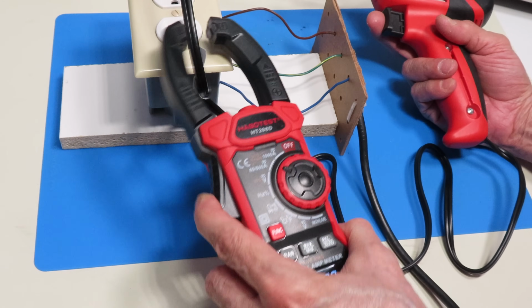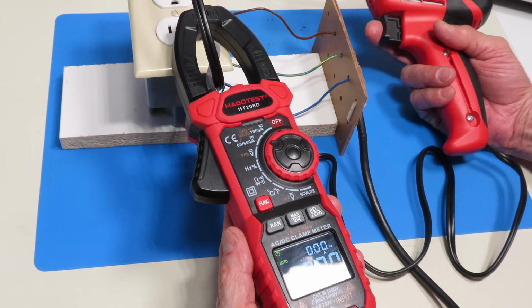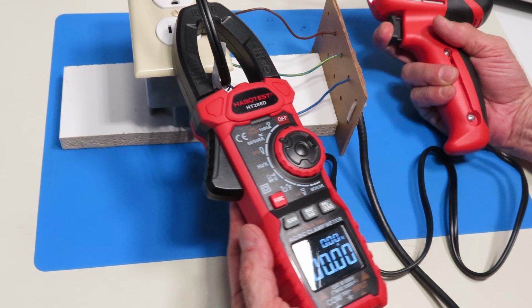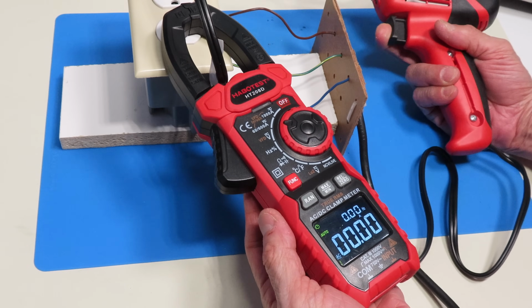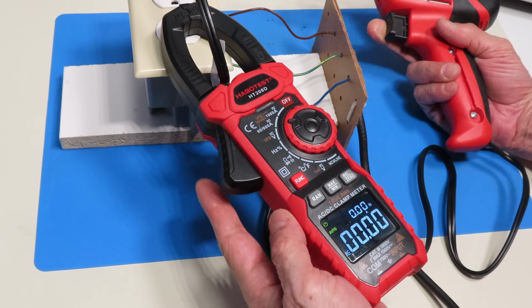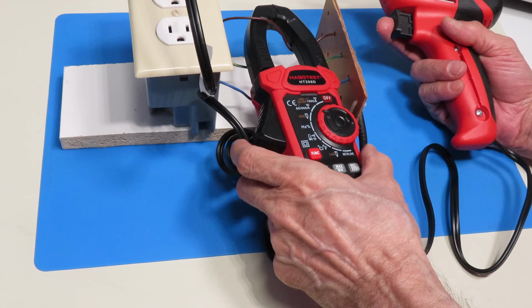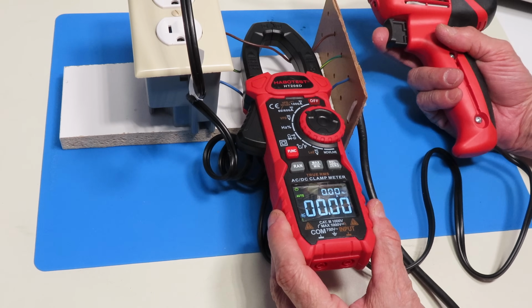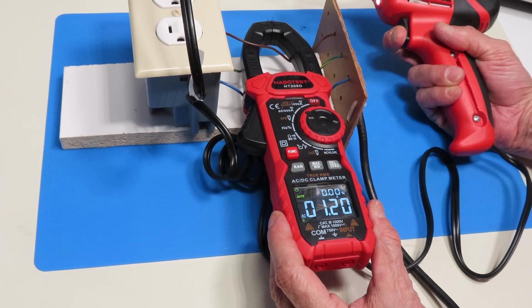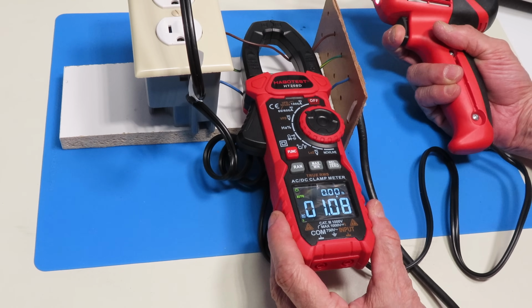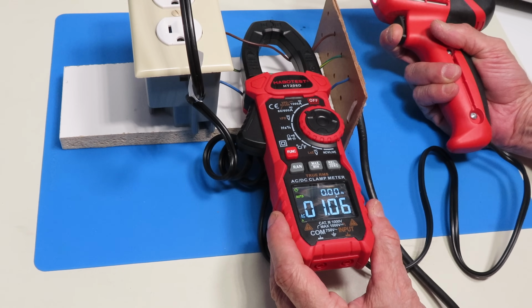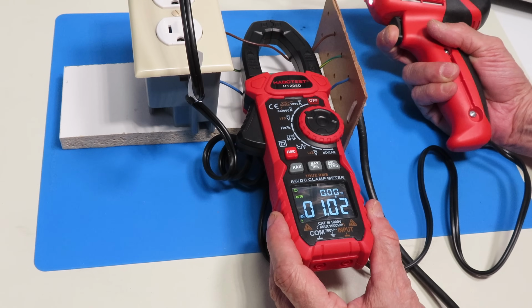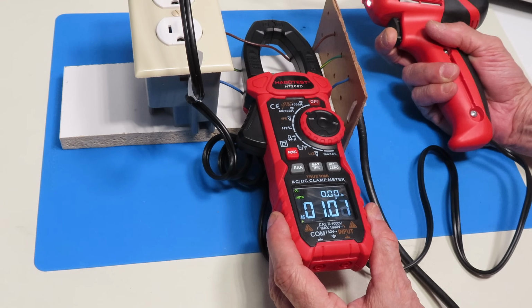First I'm going to put the meter around here and turn it on - I don't get anything at all on the meter, because that's not how it works. So I'm going to put it just around the hot lead, this one over here, and turn it on - there you go. I've got about 1.15 amperes of current, which for a 150 watt soldering gun at 120 volts is probably about correct.